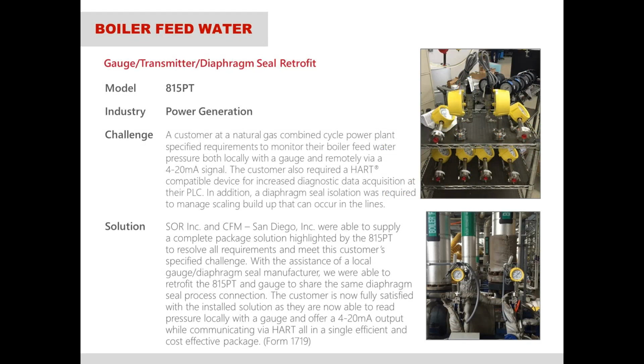This is a boiler feed water application. They needed a diaphragm seal or a gauge, as well as a transmitter output going back to their DCS system, all on one pressure port. They only had one pressure port, but they wanted local indication via a separate technology than the actual gauge. So they wanted two technologies at the same pressure port, and they have a diaphragm seal here, and then teeing off of the gauge, you have the transmitter on there as well.